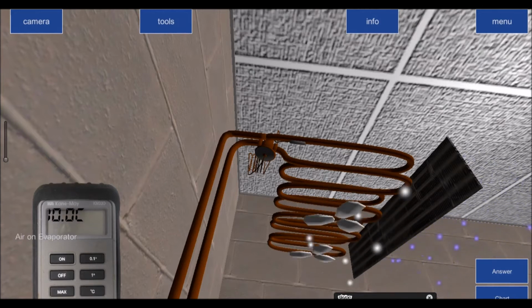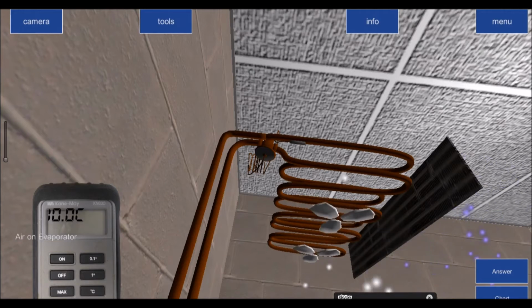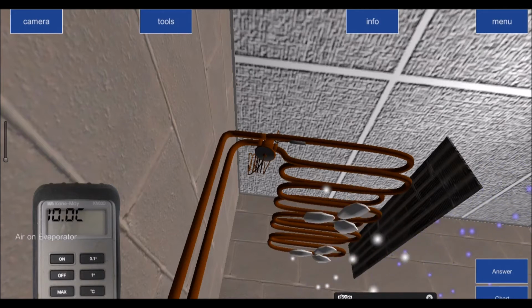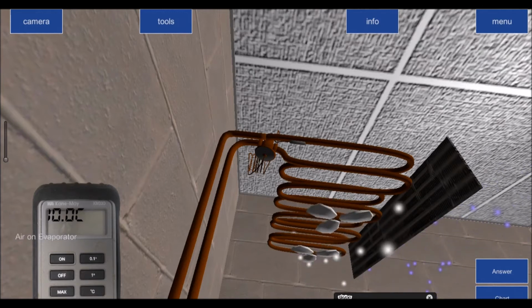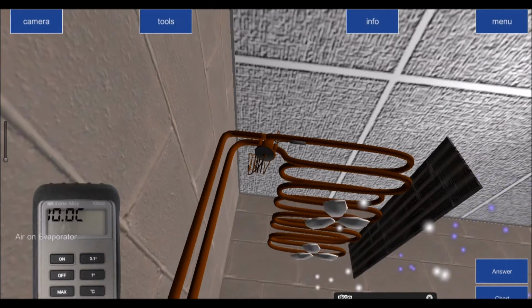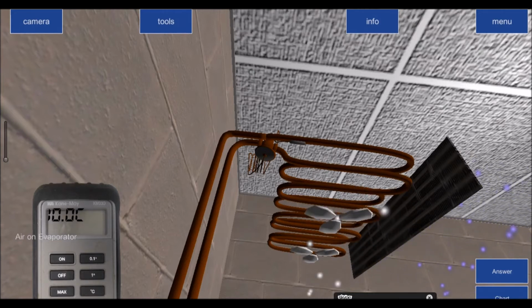I am expecting a minimum evaporating temperature of 0 degrees, because if I take 10 from 10, that gives me 0, and a maximum evaporating temperature of 5 degrees, because if I take 5 from 10, that gives me 5. If I took 6 from that, I could have 4 degrees. If I took 7, I can have a 3 degree evaporating temperature. If I take 8, then a 2 degree evaporating temperature, and 9 from that is 1 degree. So anywhere between 0 to 5 degrees would be the evaporating temperature that I'm looking for.